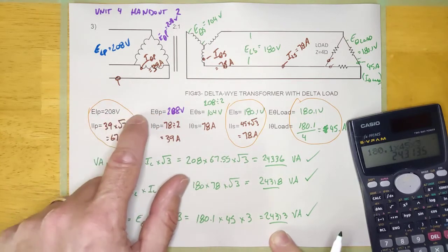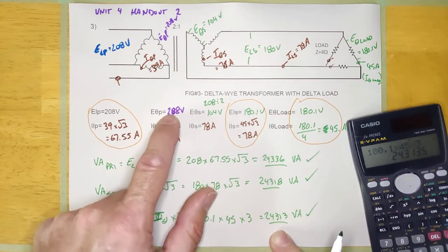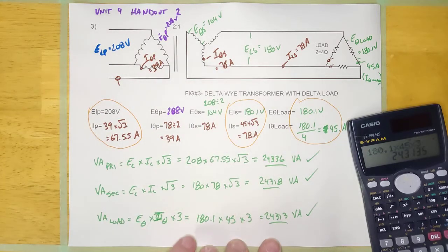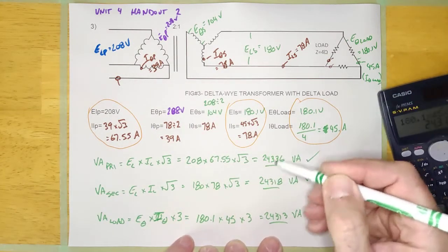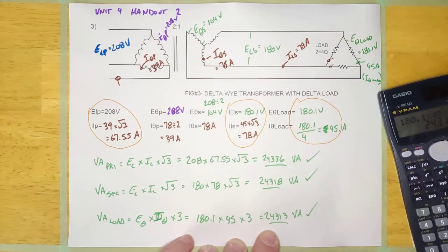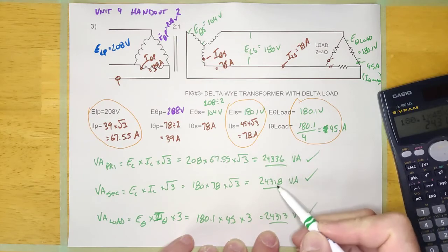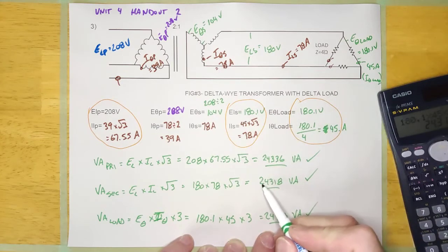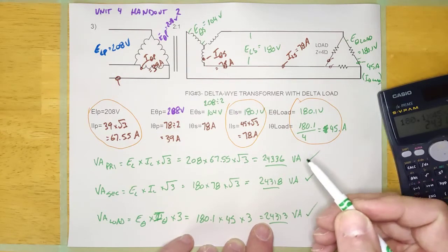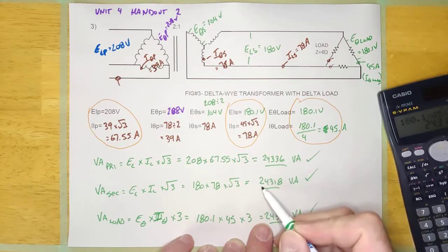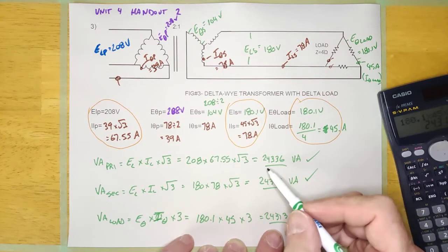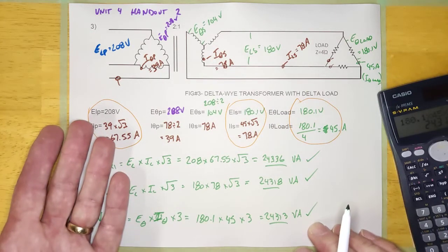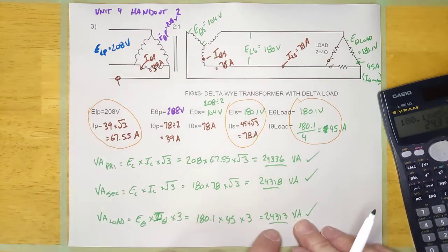Because if I had made a mistake and divided by √3 somewhere, I'd have 208 divided by √3, which is 120 — and this would be off by a lot. Everything would be off. If you made a √3 error, you'll have one of these first significant digits wrong — this will be a 3 or a 1 instead of a 2. It'll be way off — basically off by 1.73, so almost a factor of 2.